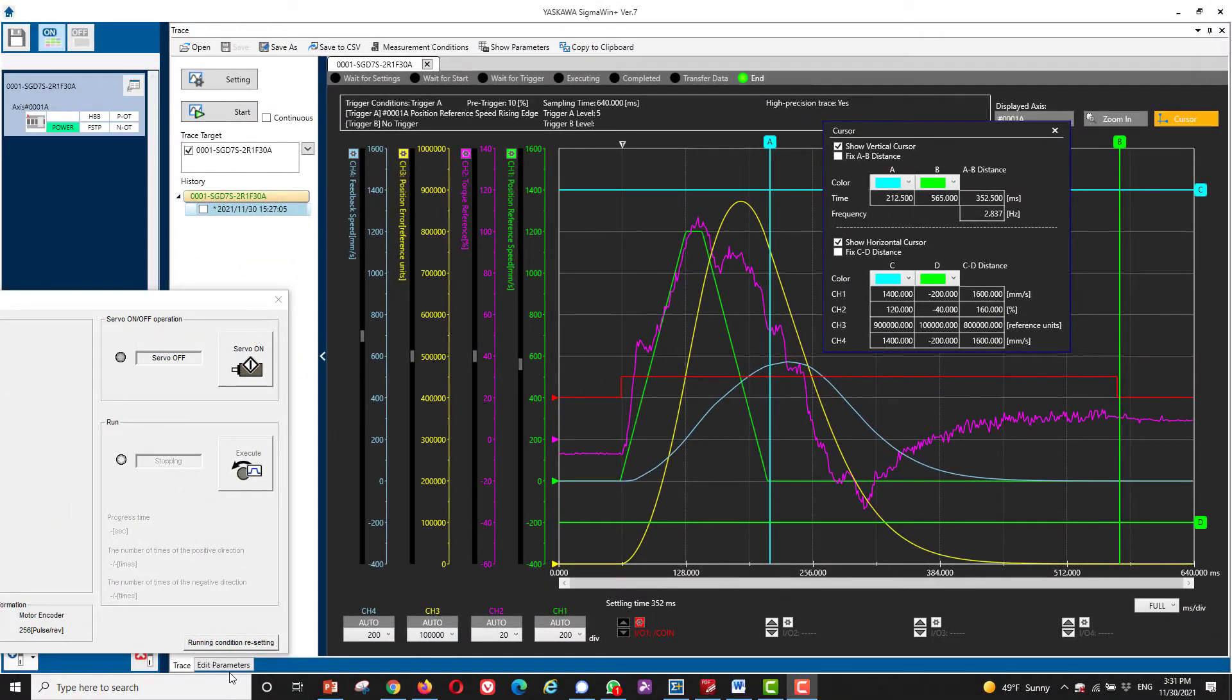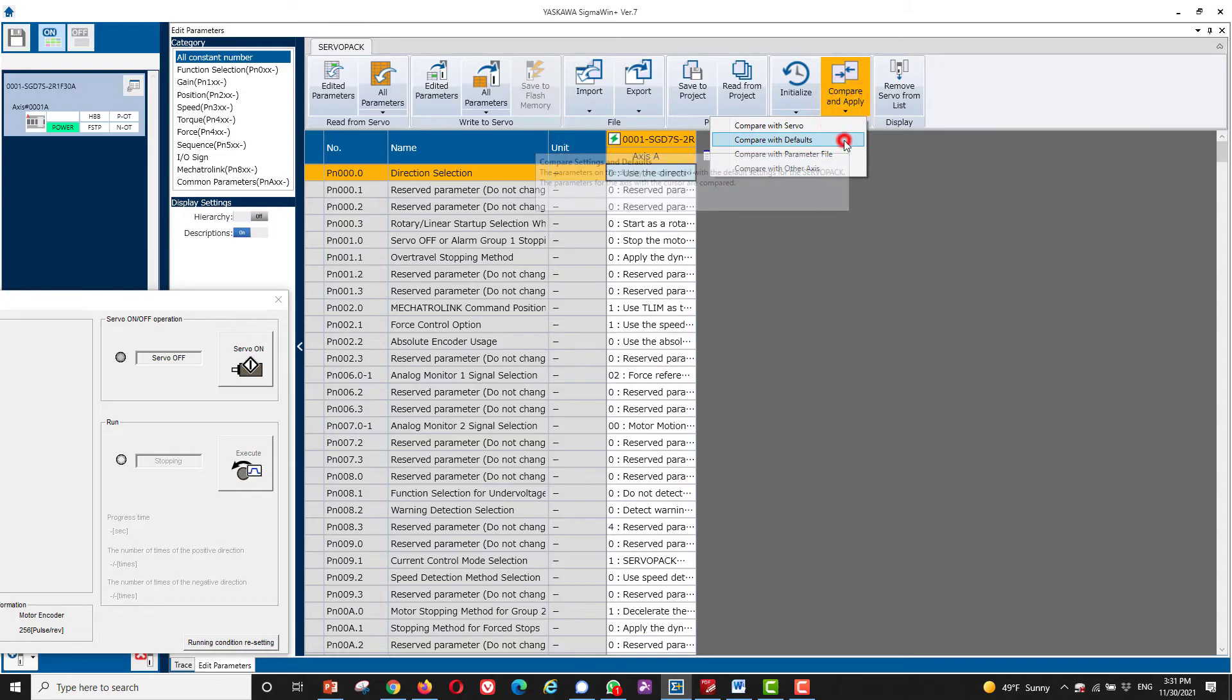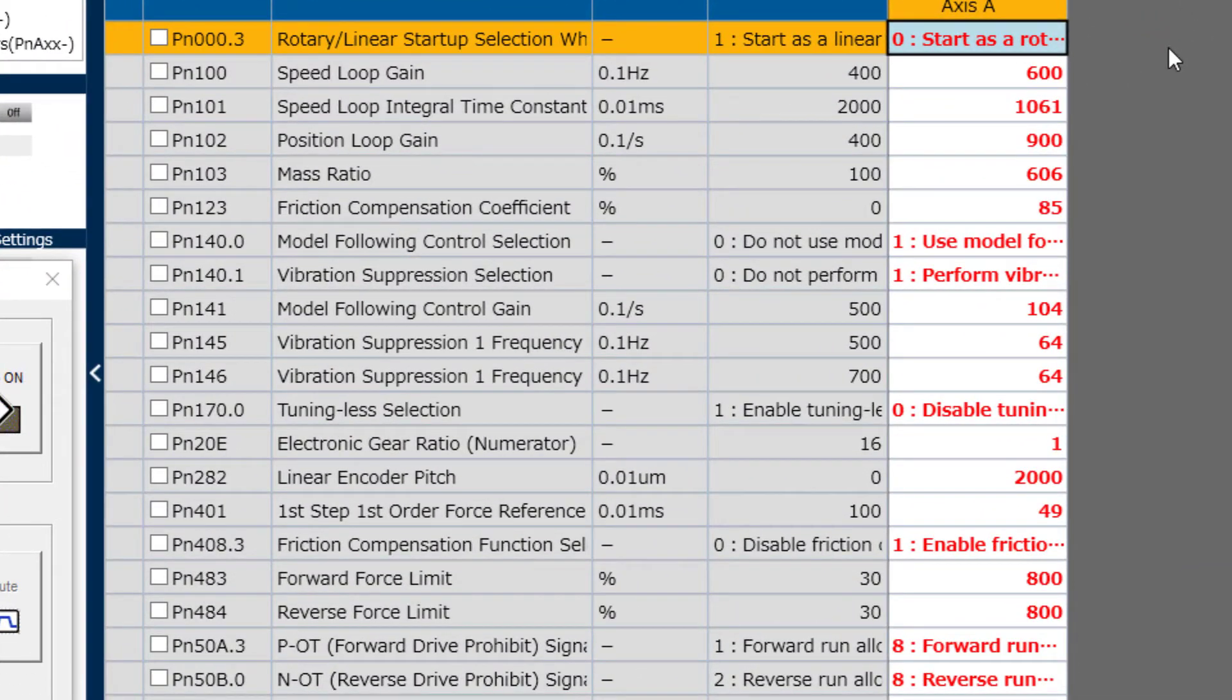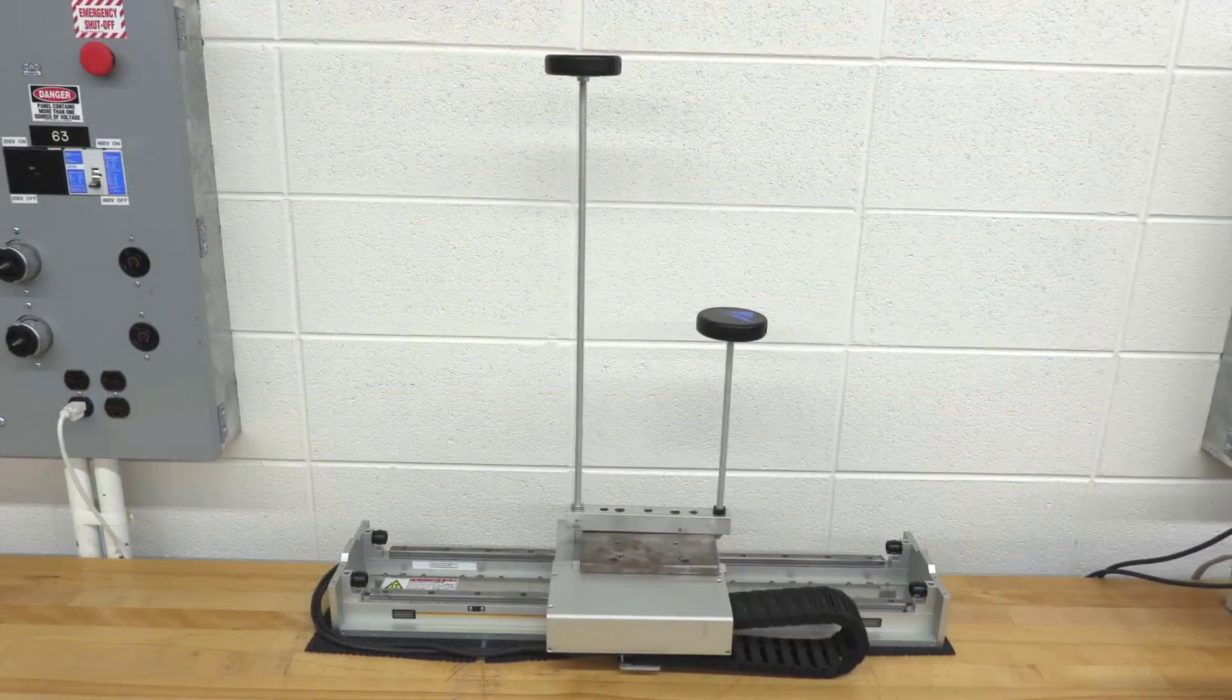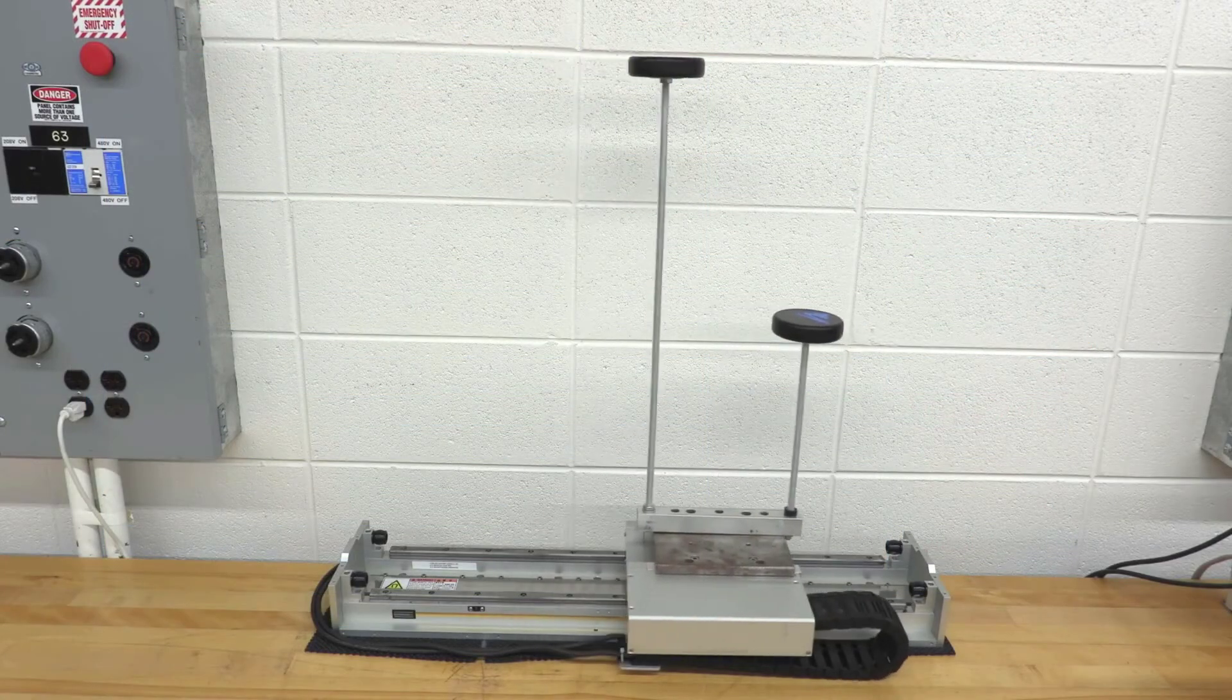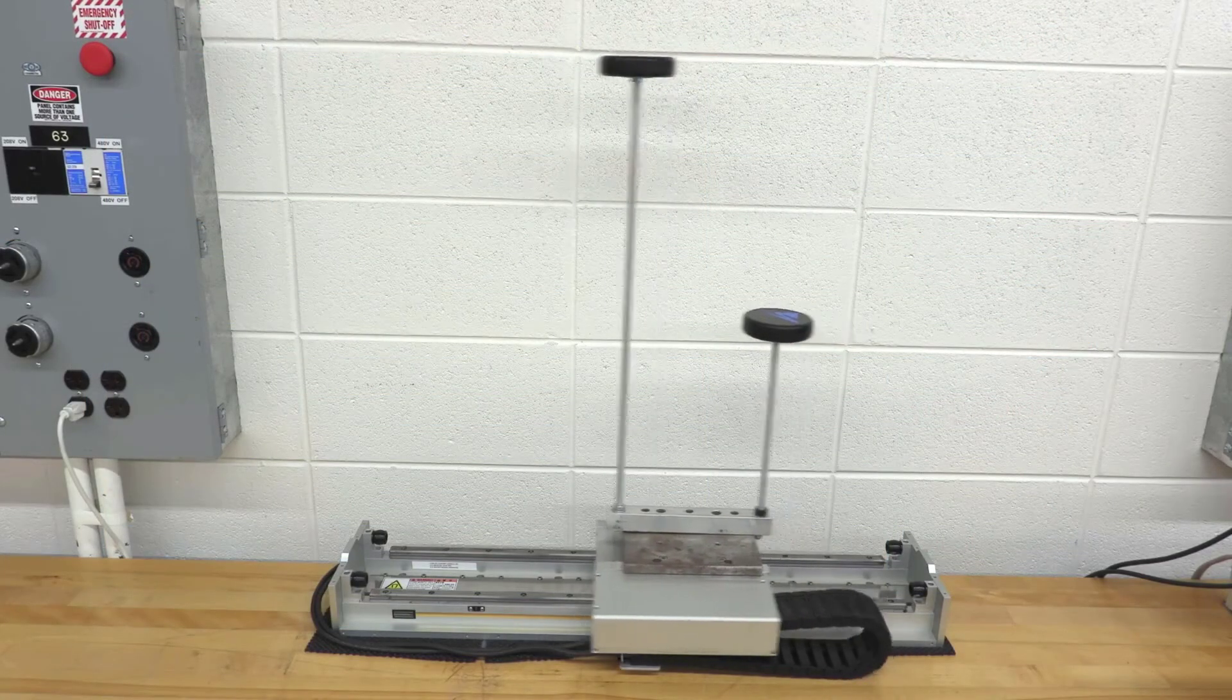If I compare the parameters to default, it reveals that quite a number of parameters have been changed by auto tuning. Among them, model following control and vibration suppression at a frequency of 6.4 hertz. I think you'll agree that the result is amazing compared to what we started with.